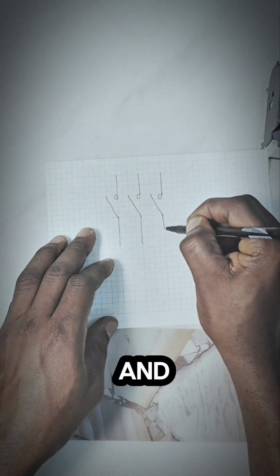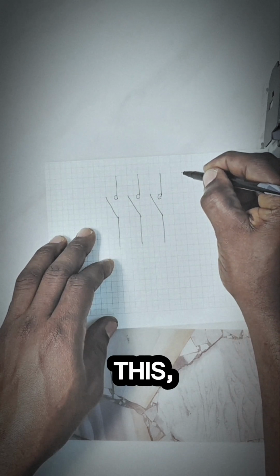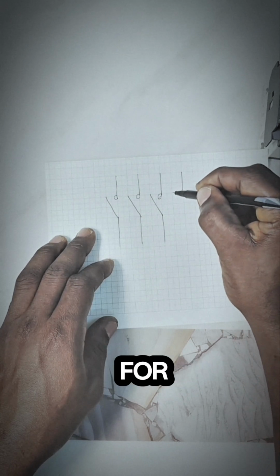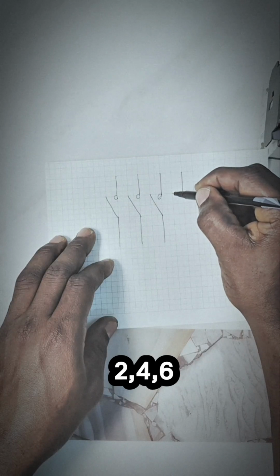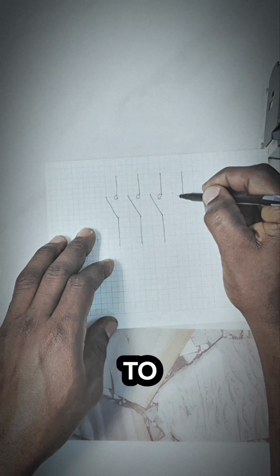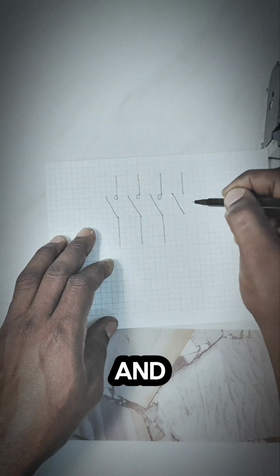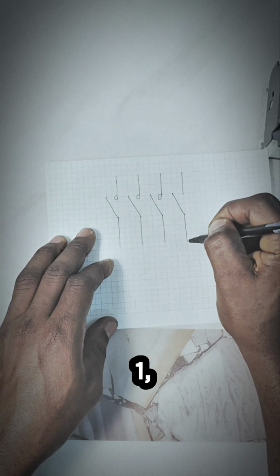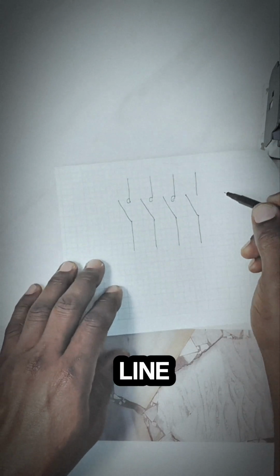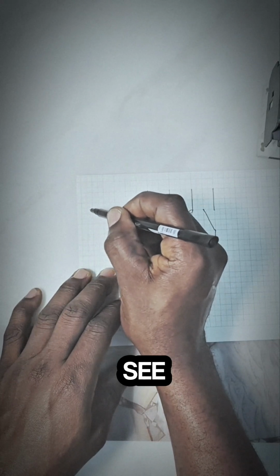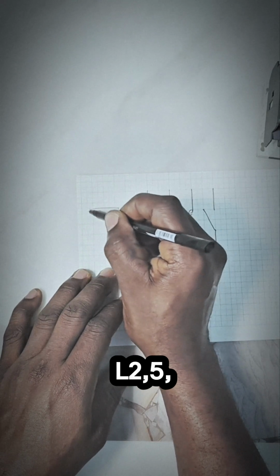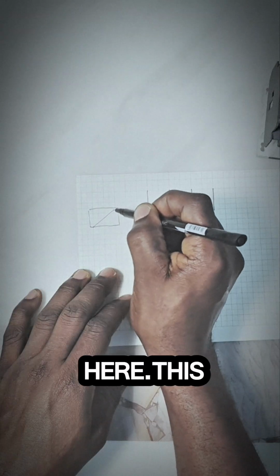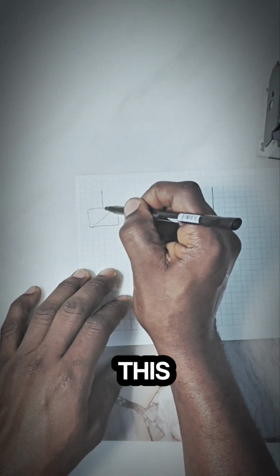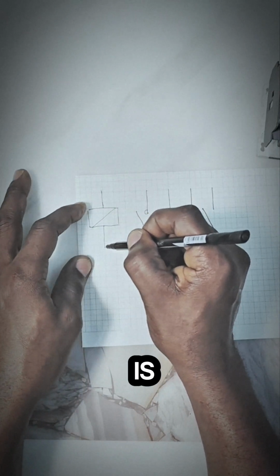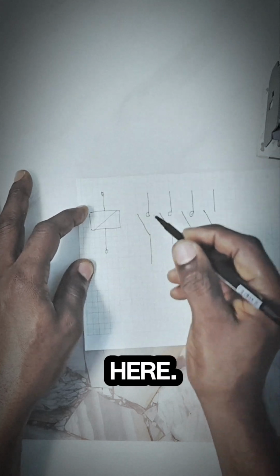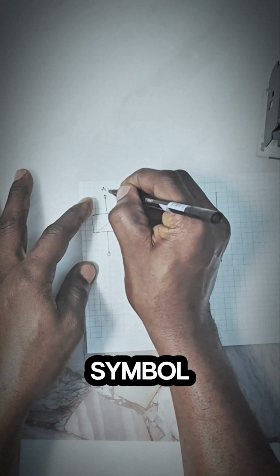So this 1, 3, and 5 are the inputs, these poles here, for power. And this 2, 4, 6 is the output that is connected to the load. And then it is further labeled: this is line 1, this is line 2, and this is line 3. That is why you always see L1 on 1, L2 on 3, L3 on 5, and then down here, this one is terminal 1, this one is terminal 2, and this one is terminal 3, just the way you have them down here. This here is the electrical symbol of this contactor.